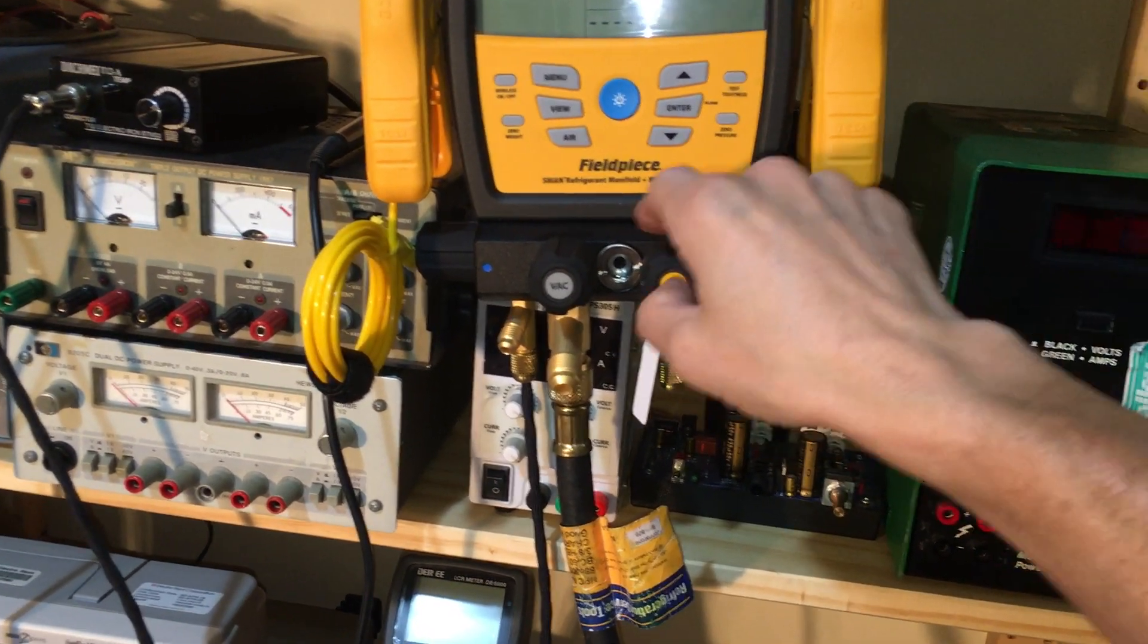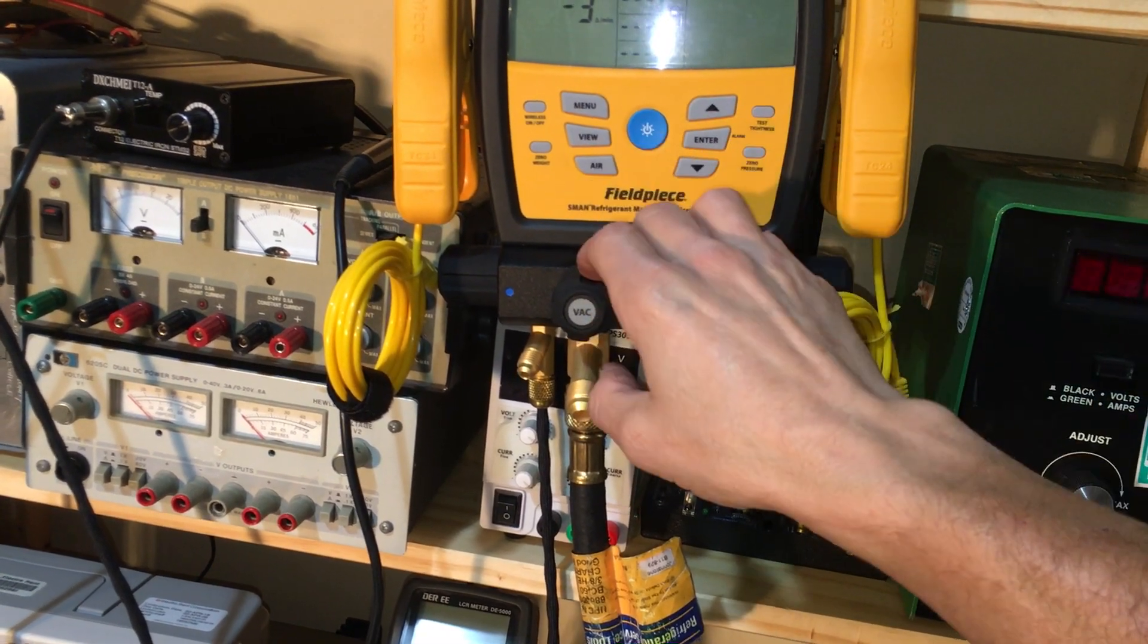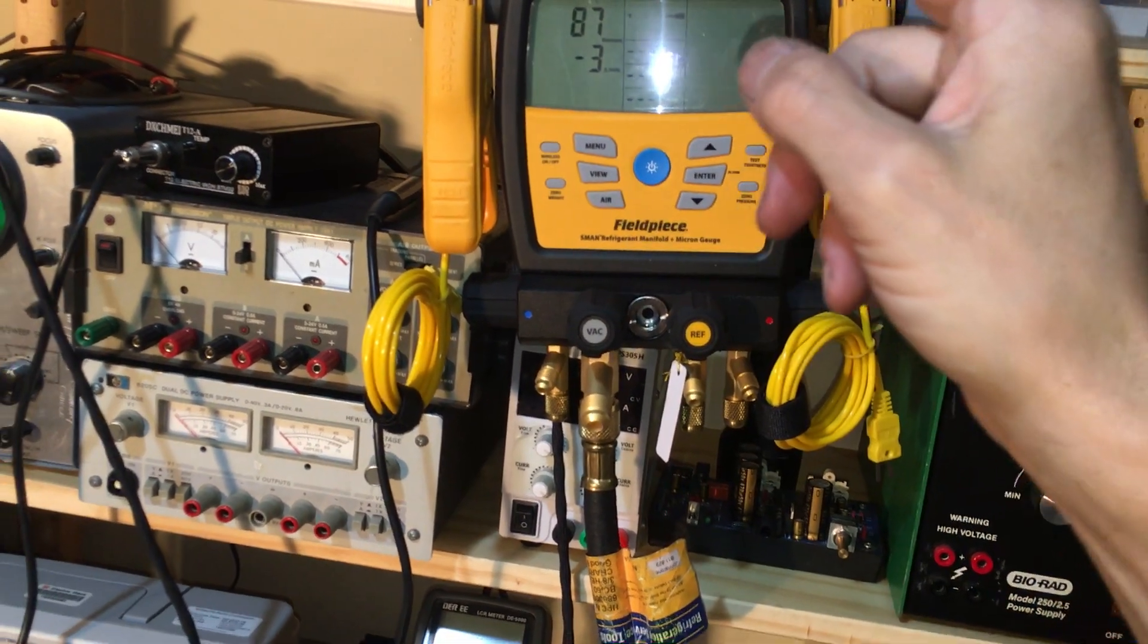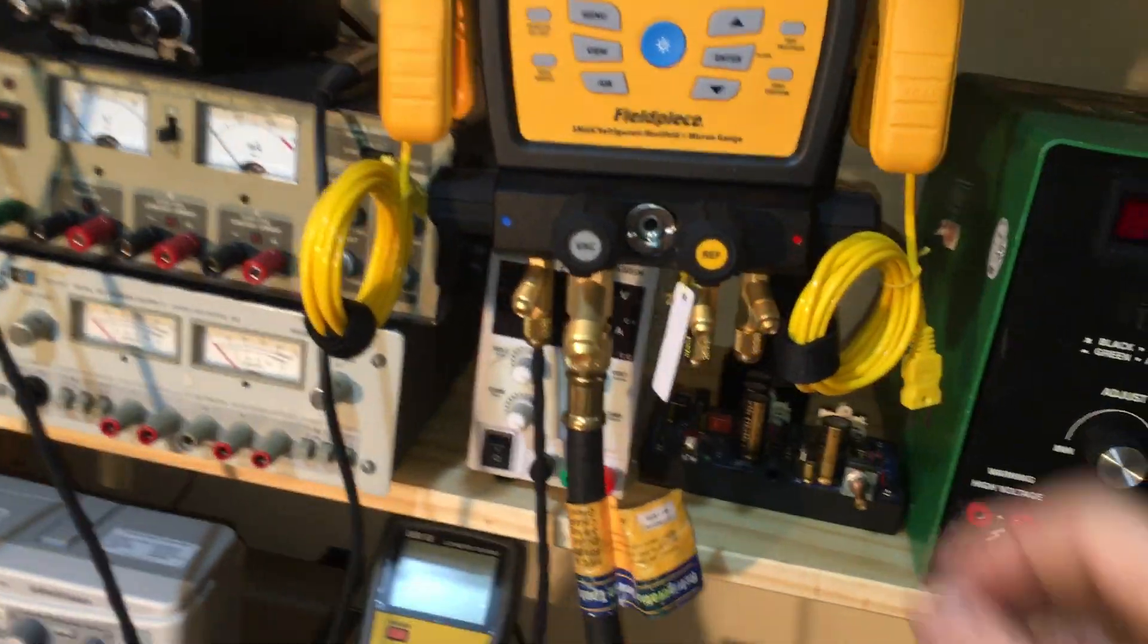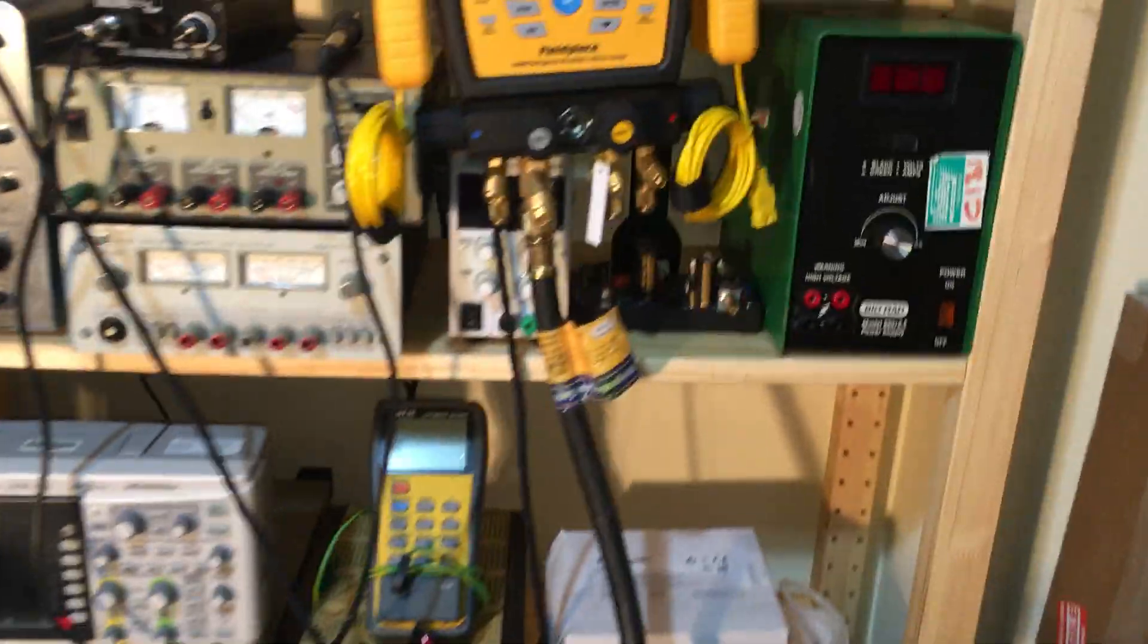I could say almost all of my gauges that I've bought usually fail this the first time right out of the box, and I have to take them apart. Then I'll use silicone grease like you see here, take the o-rings out, use silicone grease inside the valving, and then it'll pass the vacuum test after that.